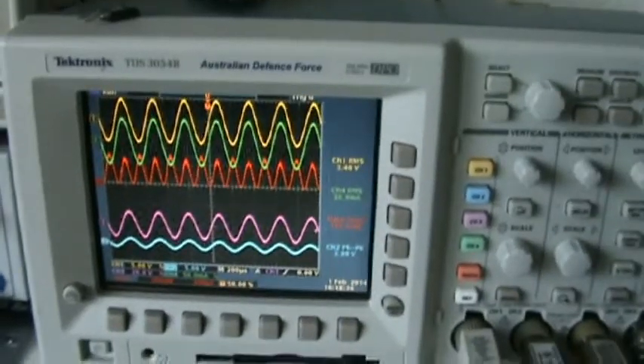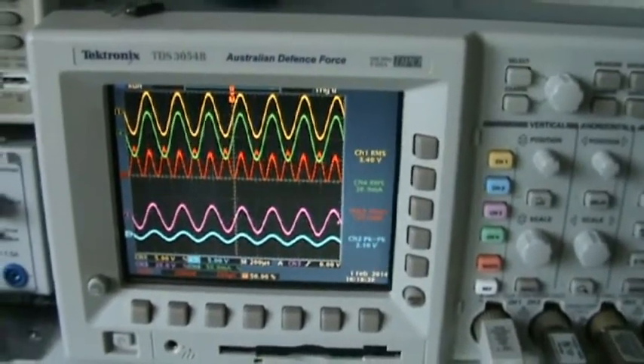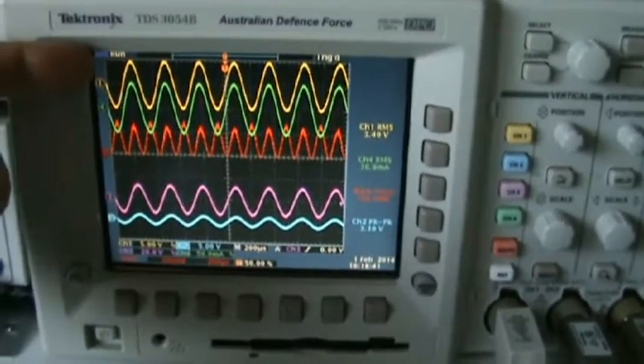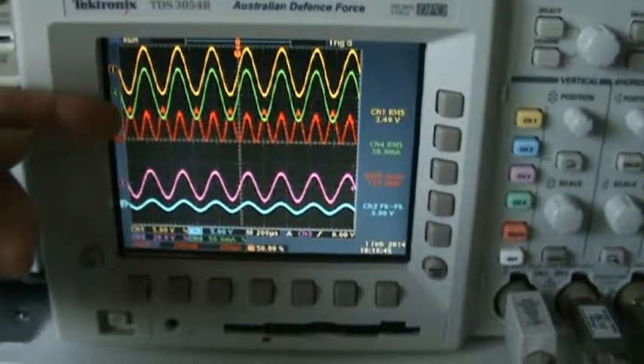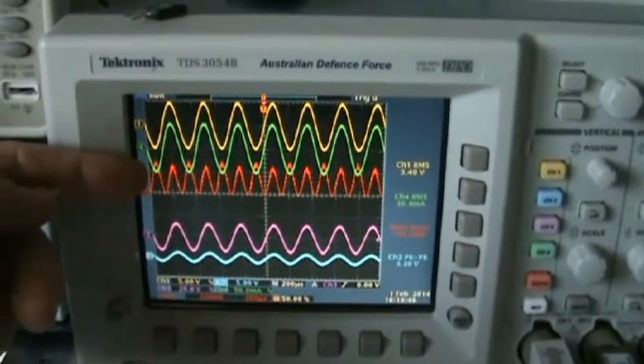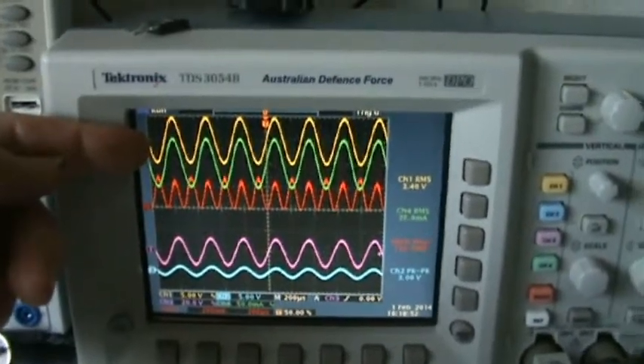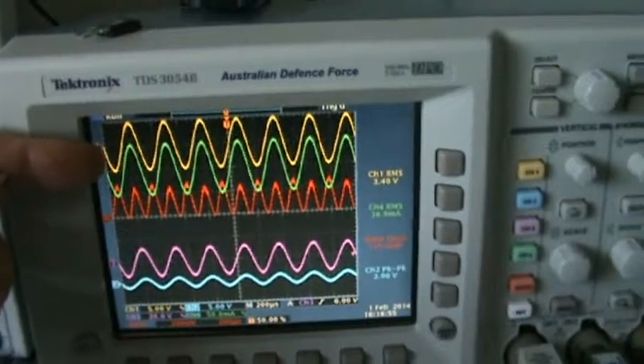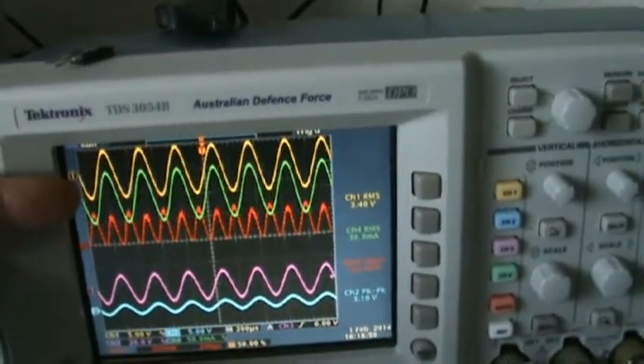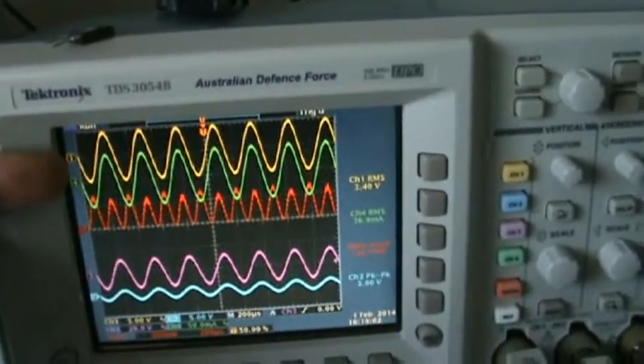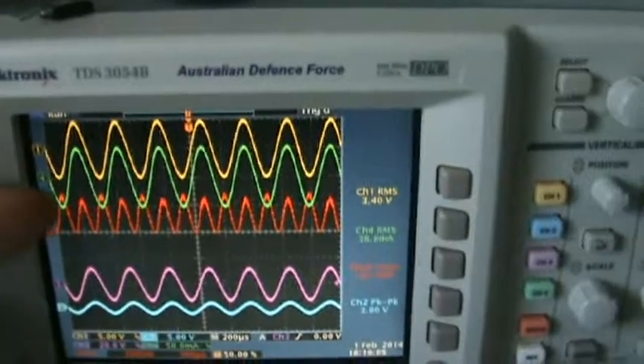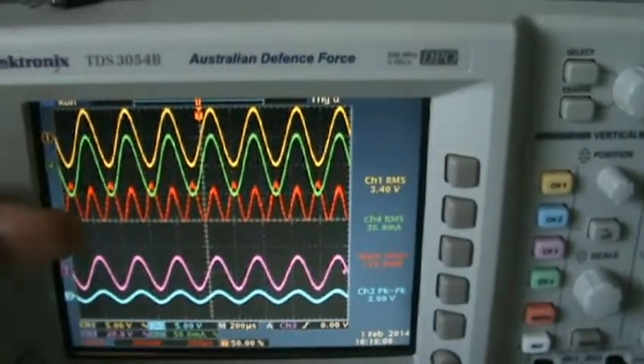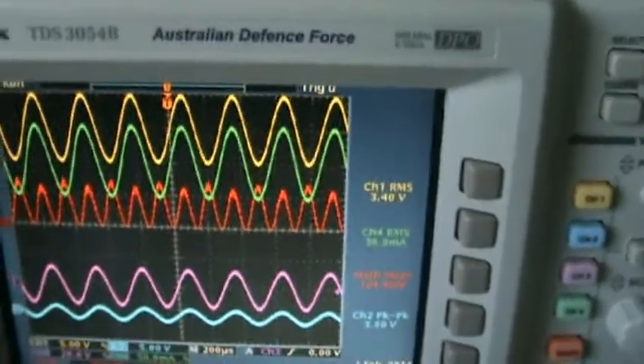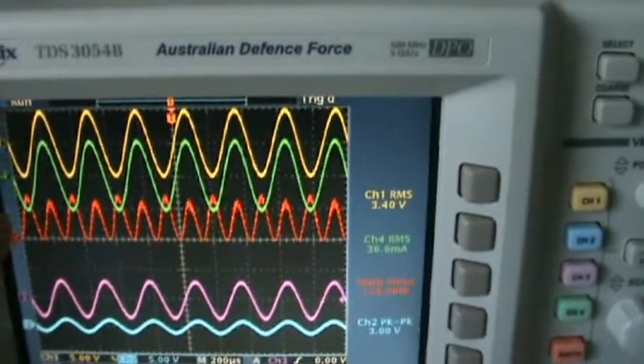And I put up the math function for the yellow and the green trace, where green is the current with the current probe, and yellow is the voltage across the right bulb, which is now lit and in resonance. The yellow trace is 3.4 volts RMS. The current is 36.9 milliamps, but because my terminator is set at 2 milliamps per millivolt, we have to multiply by 2, so it's something like 72 milliamps. And the math trace is channel 1 times channel 2.